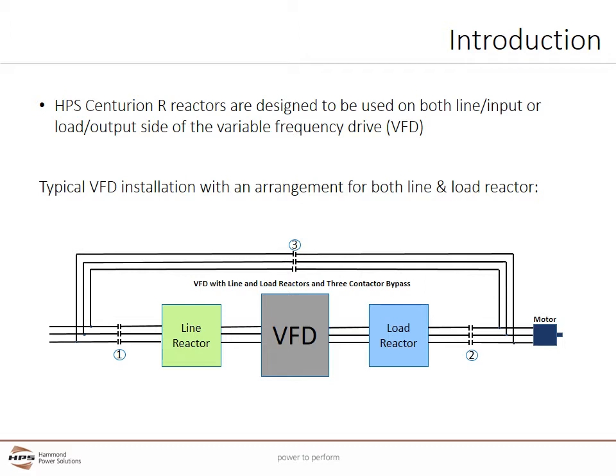HPS Centurion R Line Reactors are designed to be used on both the line or input side of a VFD and the load or output side of the VFD. There is no derating required. The same reactor size can be used on either the load or line side. The diagram below shows a typical VFD installation with reactors on both the line and load side.